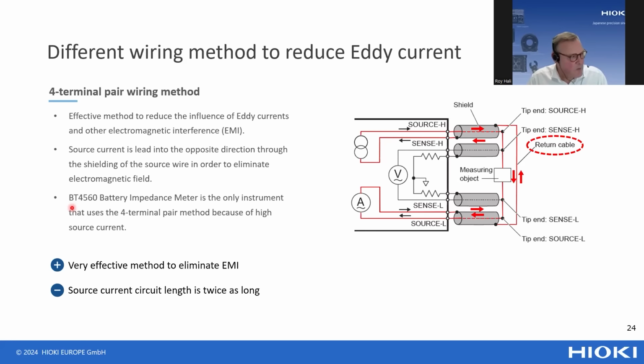What's the main difference between the normal 4-wire measurement and the 4-terminal pair wiring method? Well, the main thing that is different is that we use coaxial cable instead of twisting wires.